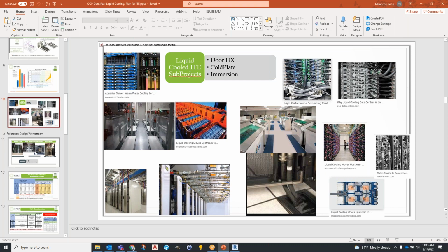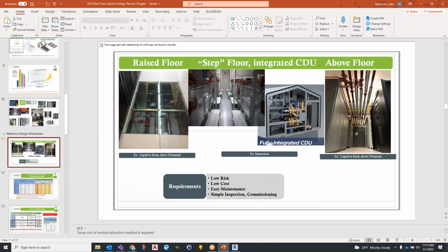If I go to this other solution here, which is in a modular container, the pipes are running underneath the floor, I believe, but again, cabling, same thing, overhead could be a problem. It's also true here. So the top of things, especially for immersion, are important. You can see here, if you need to get to the top surfaces of these items, you've got a lot of piping in your way. So you may be able to still do it, but certainly a consideration.